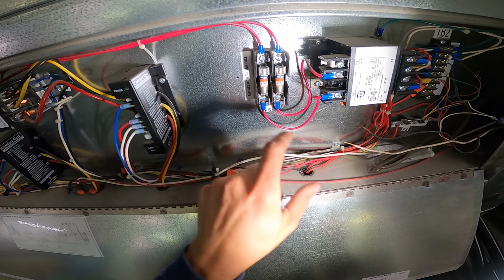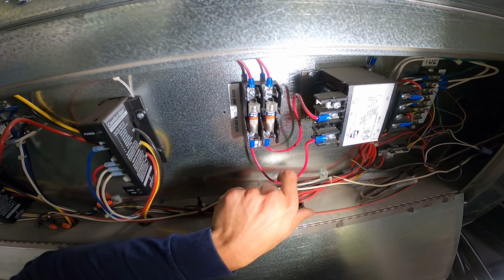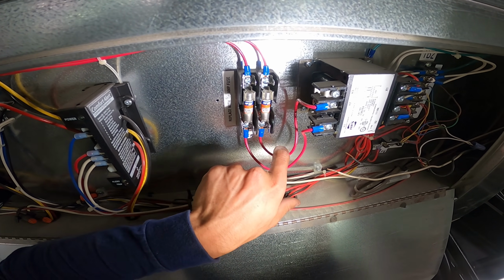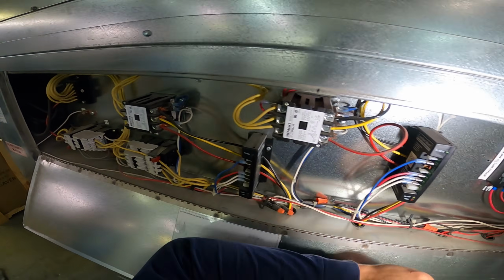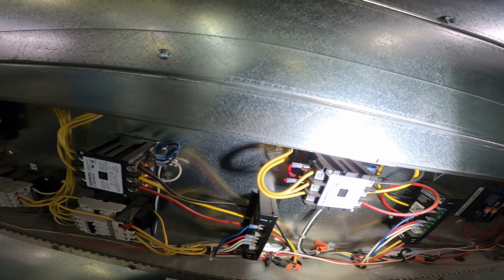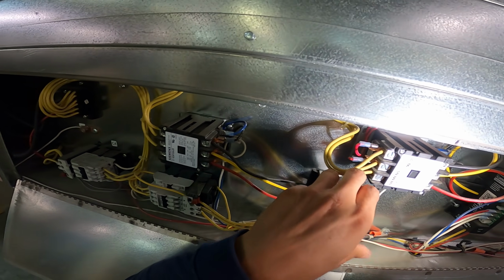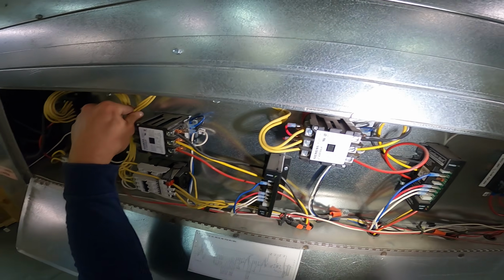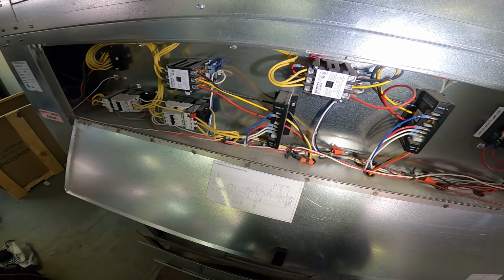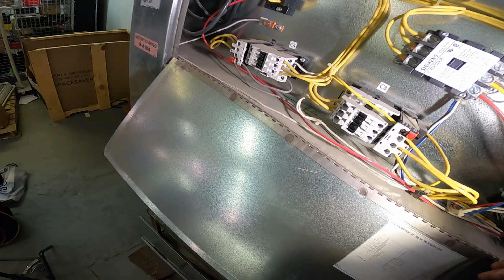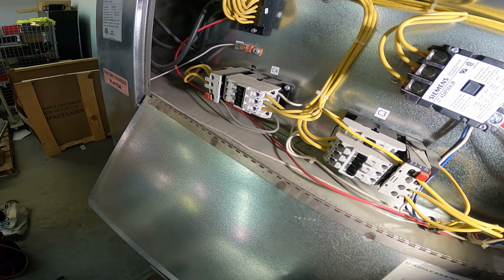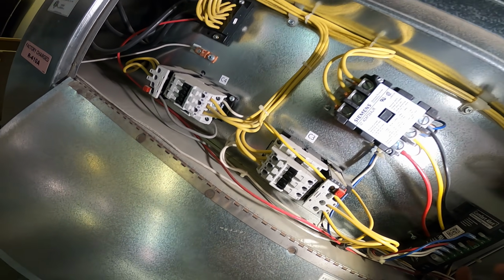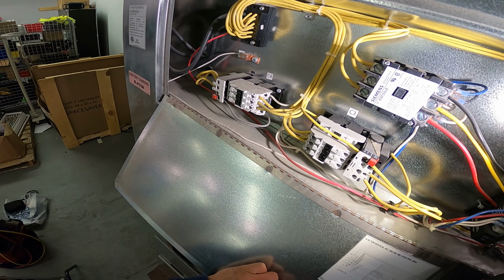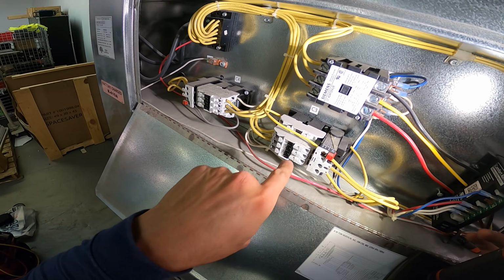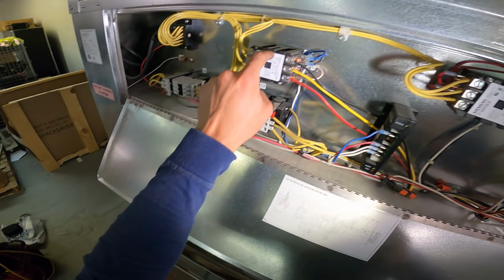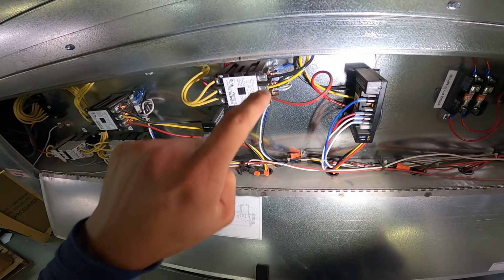If we follow these wires, here's another fuse block with 2 fuses, except this is protecting our line voltage. So we have 120 volts in each leg to ground, and these fuses protect that circuit. From there, we'd feed power to one side of this contactor, which is gonna be our line side, and at the same time, we're gonna feed the other side of this contactor. So these 2 contactors are for our compressors. Then these 2 right here are actually motor starters, which the only difference is it's basically a contactor with a set of overload contacts with extra safety. So these 2 are basically our starting component, one is for your evaporator fan, the other one is for your condenser fan. And then this contactor is for one compressor, and then this contactor is for the next one.